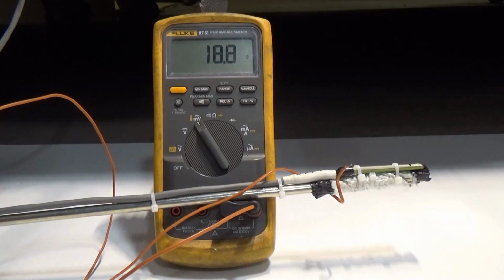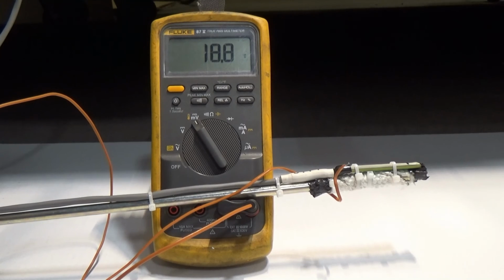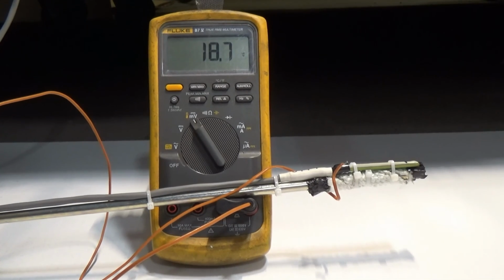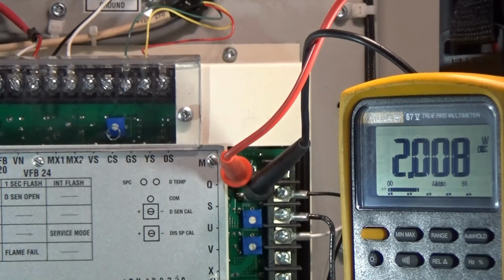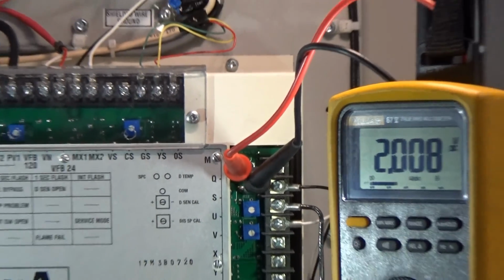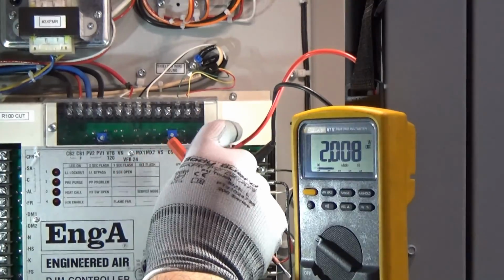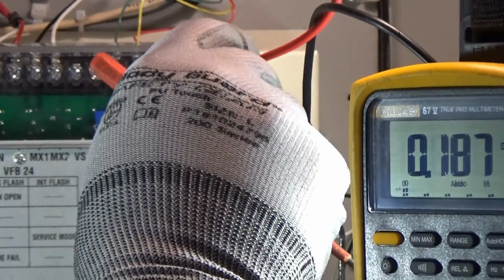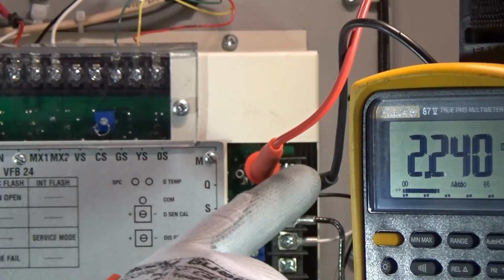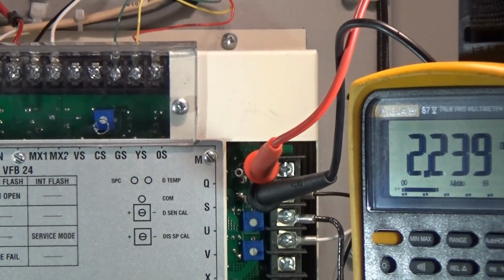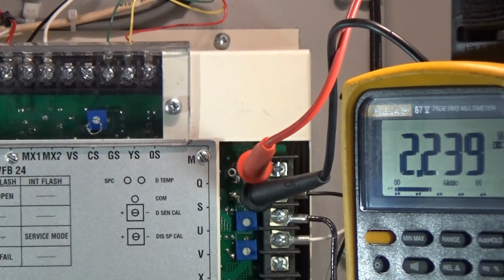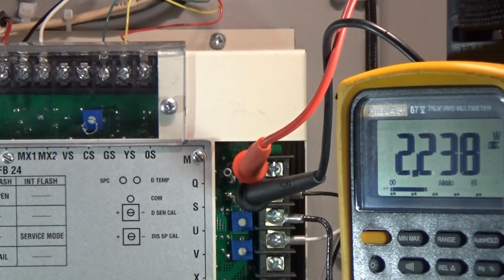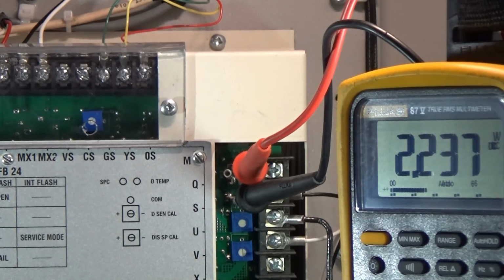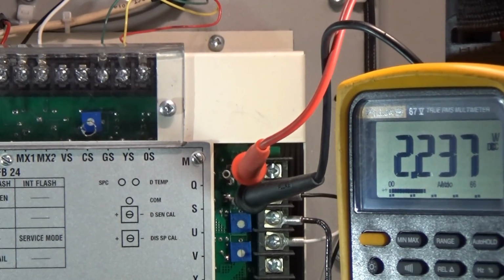To calibrate the discharge air sensor, accurately measure the temperature at the sensor. Make sure the temperature at the sensor is steady. With your multimeter still set for volts DC, move your positive lead to the pin on the right for discharge temperature, keeping your neutral lead in common. This will give you a readout of your discharge air sensor temperature. 1 volt DC, again, is equal to 10 degrees Celsius. So our sensor is reading 22 degrees. However, our other reading was actually 18 degrees.